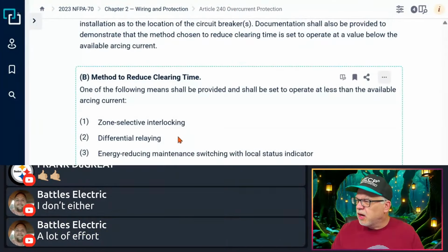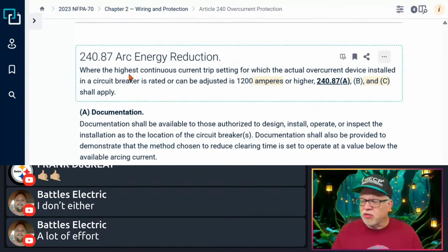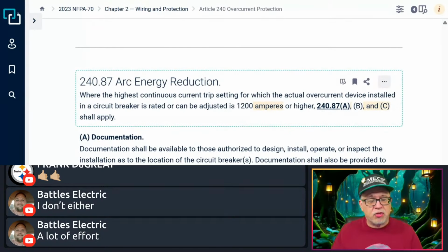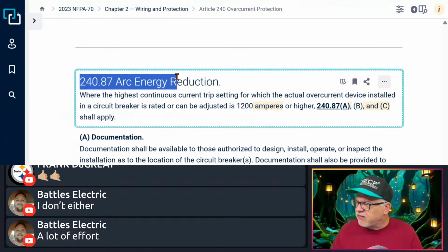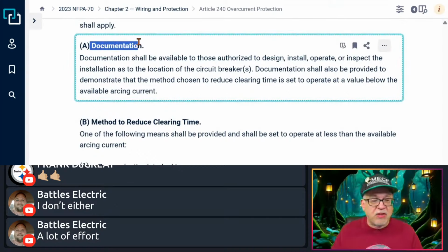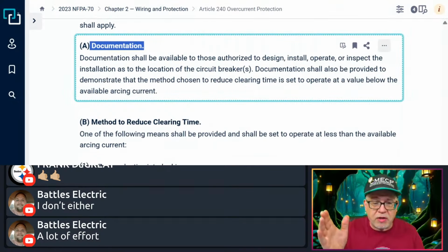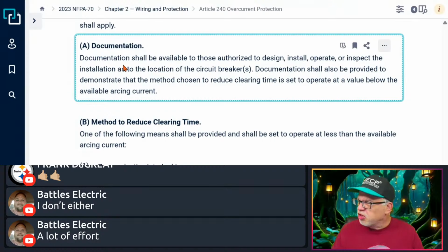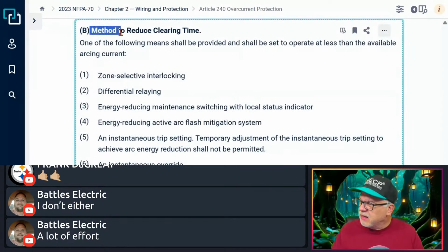Where do we get that in the NEC? We're looking here under arc energy. You might get some drawings or some project that requires that you reduce that arc energy. Okay, so that is 240.87. Obviously, you're going to provide documentation on how this is achieved so the AHJ can see that you're applying it. Usually, the manufacturers of the equipment will provide this documentation because they're providing a method of achieving this as part of the equipment. So you could show documentation on how this is to be done and how you're reducing the clearing time, or you could have a method of reducing it.